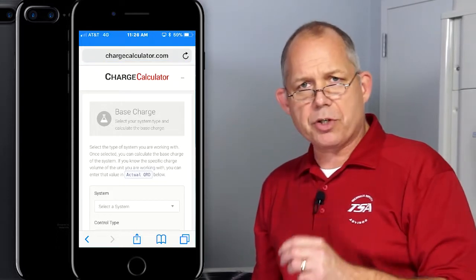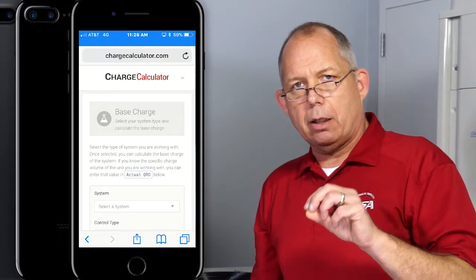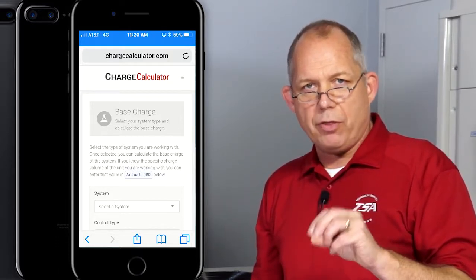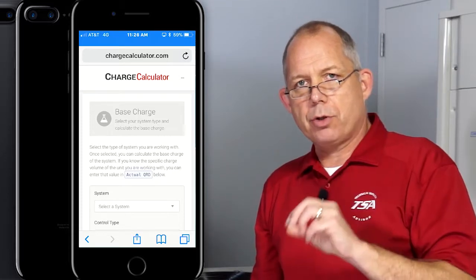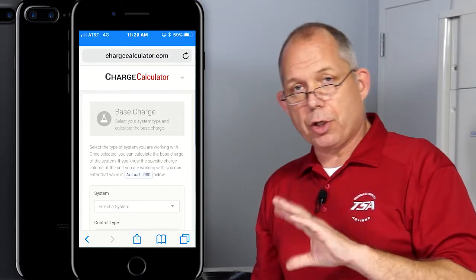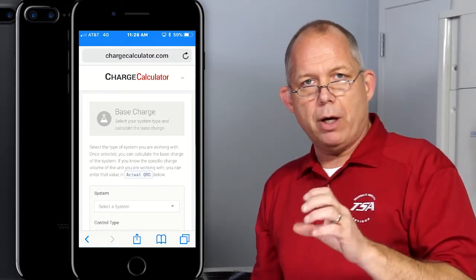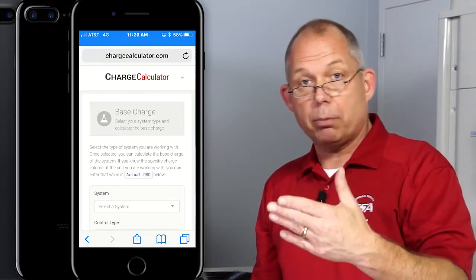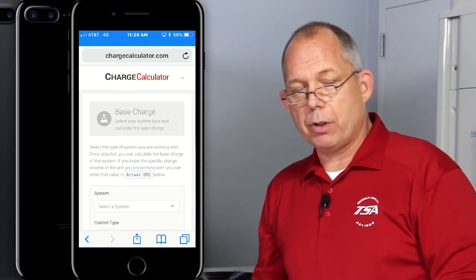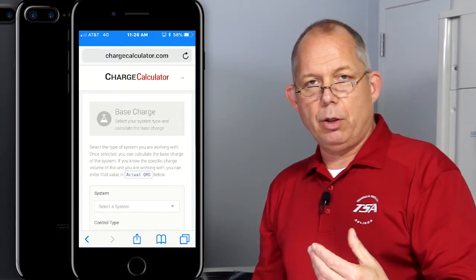First thing it's going to ask you for is your base charge. As always at Nortech Global HVAC, we want you to refer to the QRD that came with the unit to ensure that you have the correct charge. If you're unsure of that charge, we can look at that a little bit later in the app. But if you're unsure if you have the correct factory charge, if you're coming up to troubleshoot or diagnose a system that may have a refrigerant problem, remove the refrigerant from the system and refer back to the QRD.